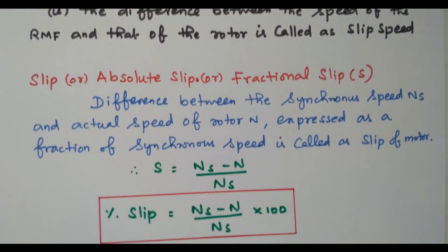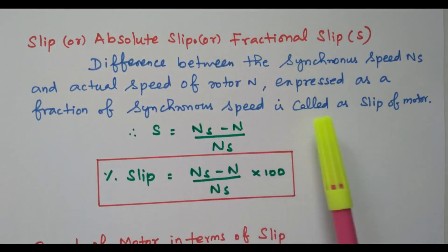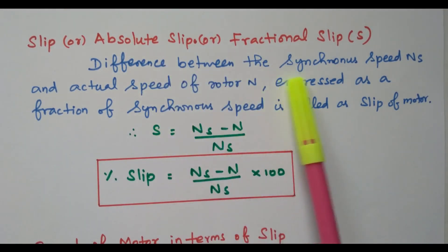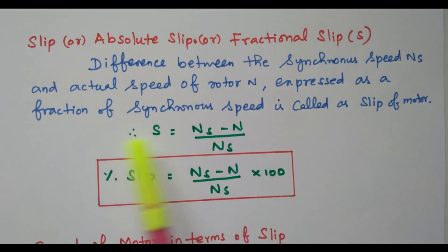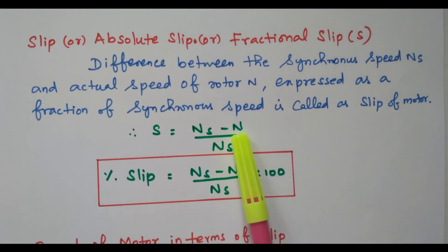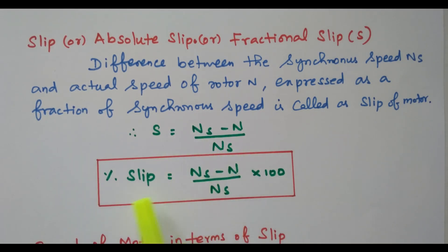The definition of slip: slip is also called absolute slip or fractional slip. It is the difference between synchronous speed and actual speed of the rotor, Ns and N, expressed as a fraction of synchronous speed — that is (Ns minus N) divided by Ns. For percentage slip, multiply by 100: (Ns minus N) divided by Ns, into 100.